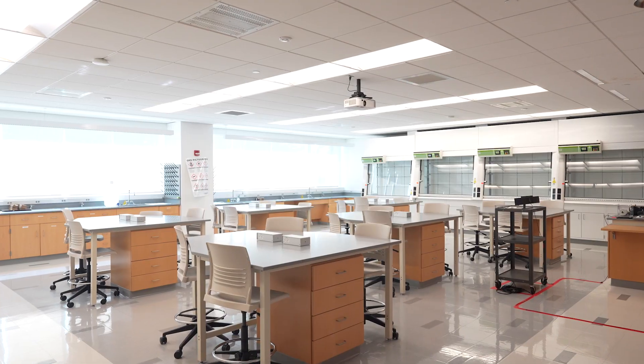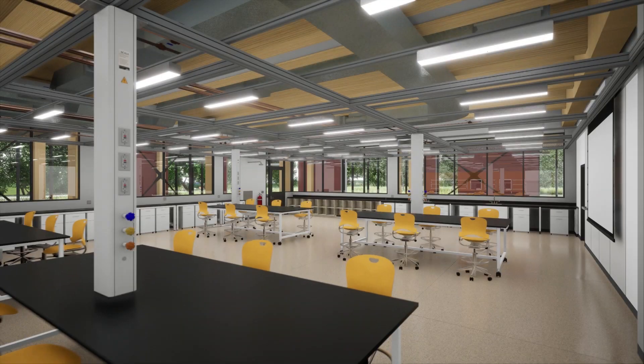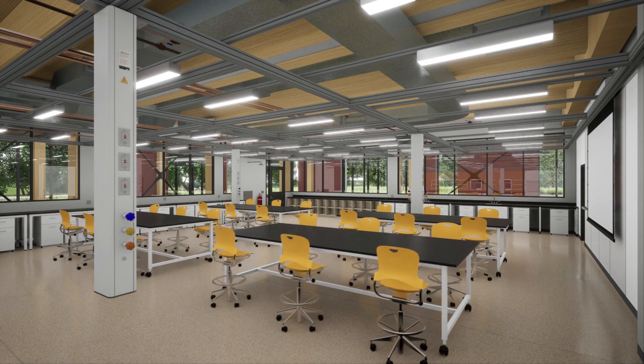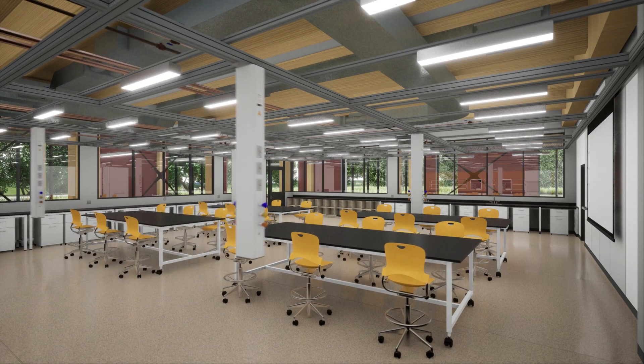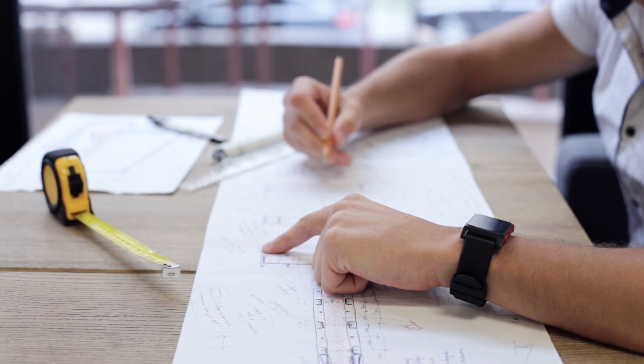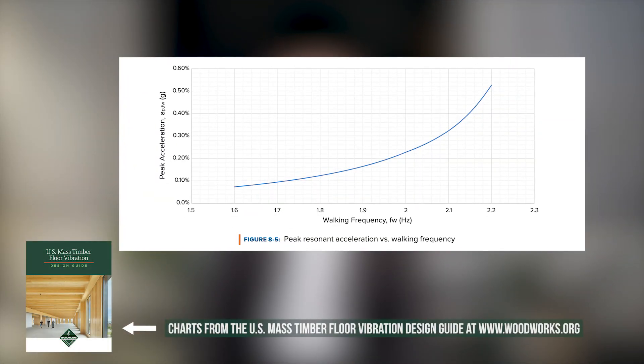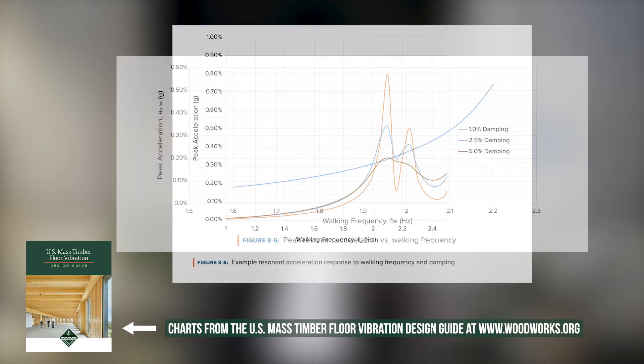The planning dimension we use is an 11-foot module, which provides for lab benches on either side of a five-foot aisle for safety. There are a few unique aspects of laboratory buildings that structural engineers must consider. One of the primary aspects is floor vibrations — there are requirements for particular types of equipment that set limits on the maximum peak velocities the floor system would exhibit under excitation.